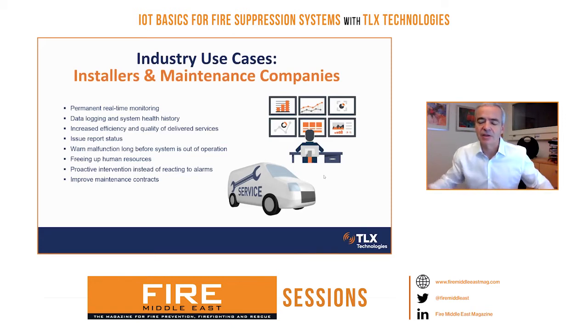Instead of having a customer calling and saying, hey, I have an alarm, the system is out of operation, now it'd be the installer calling the customer and saying, you have a problem in the second cylinder in the first row, don't worry, a van is on the way with a spare and we'll repair that. So what are we doing here?